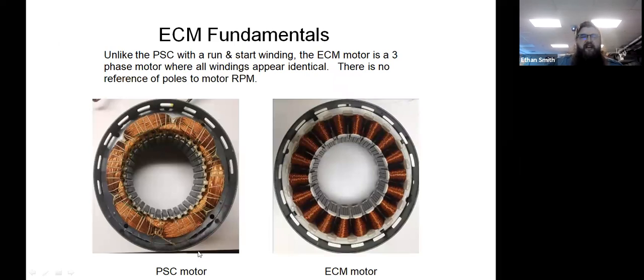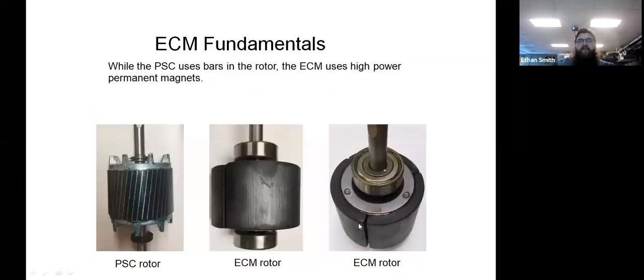So just a side-by-side comparison of a PSC motor here and an ECM motor. Because we're dealing with 3-phase, we've got no start winding. We're simply alternating coils in here. So this one is about a 4. No, it's a set. No, it's not. I'm screwing up here. 1, 2, 3, 4, 5. This is, I think, a 6-pole 3-phase motor. So we've got 6 repetitions of the 3-phase. I'm too lazy to count, but I think it's 6.